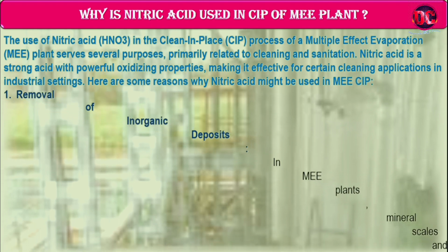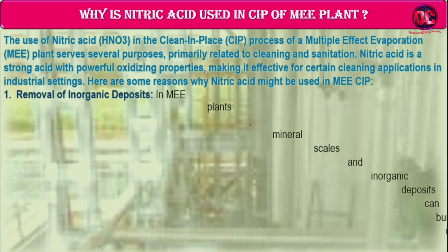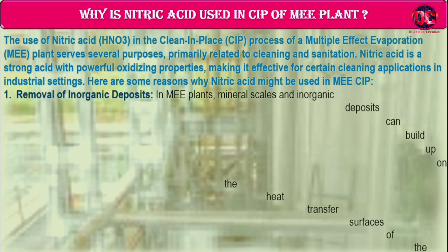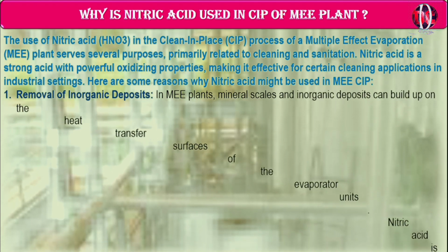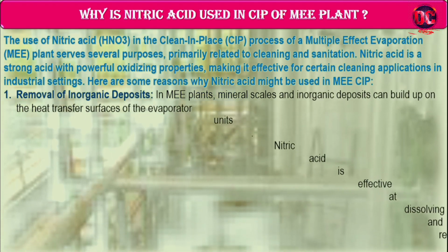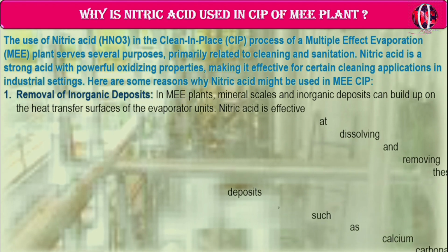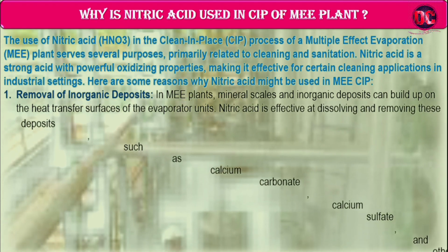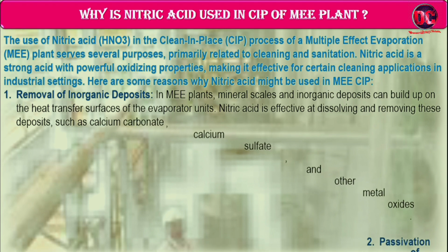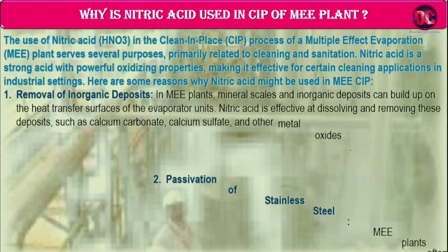1. Removal of inorganic deposits. In MEE plants, mineral scales and inorganic deposits can build up on the heat transfer surfaces of the evaporator units. Nitric acid is effective at dissolving and removing these deposits, such as calcium carbonate, calcium sulfate, and other metal oxides.